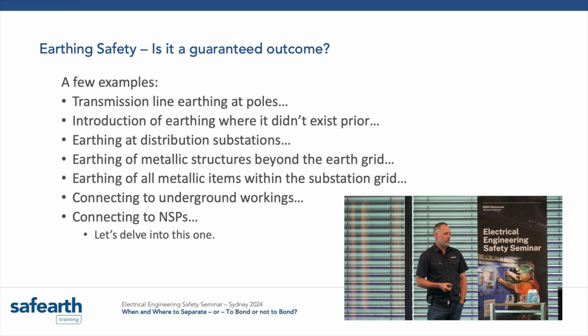Well, suddenly they needed to create a cable design. Suddenly the cable design was horrible, and you've got all these hot spots now along that entire route where you never had them if an earth fault was to happen. So it's kind of one of those things that we think, oh, we're just going to earth stuff, yoo-hoo, great. Doesn't always work out.